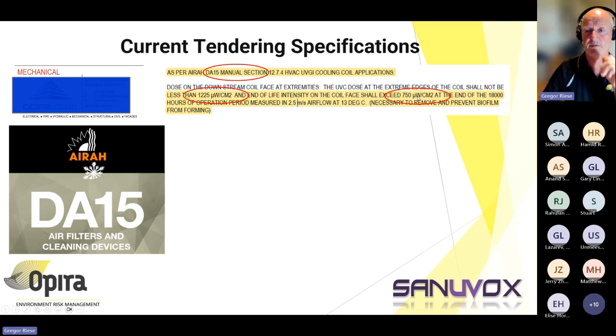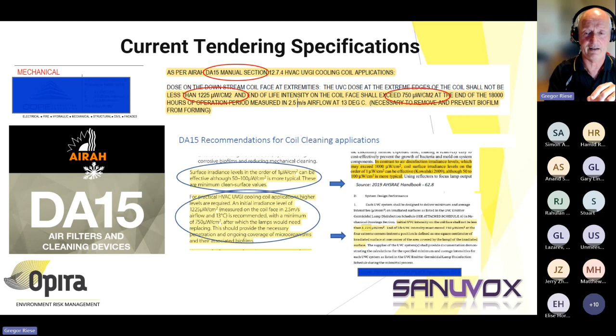DA15. This is the first part of DA15. So DA15 talks about the 50 to 100 microwatts being minimum clean surface values, and that's straight out of the ASHRAE handbook. But then the second part of DA15 goes on, and I've copied this word for word, and I'm not going to read it out to you, but it's word for word out of one of the Australian suppliers of UVC lamps, out of their guide, which is available on Amazon, which is very helpful. But they've nominated much higher numbers, and we're scratching our heads as to why you'd want such high intensity on the coil face. But we've got theories for why, and we'll just explore quickly how we've ended up here.